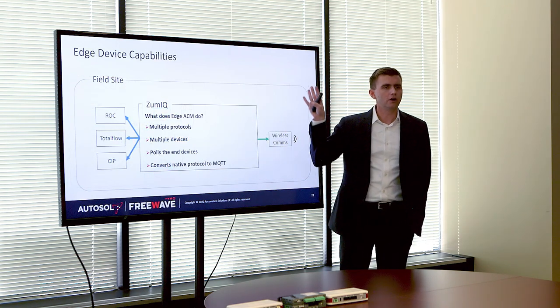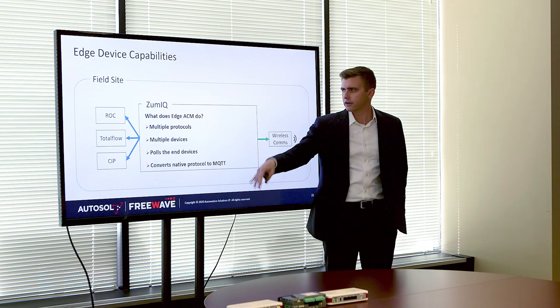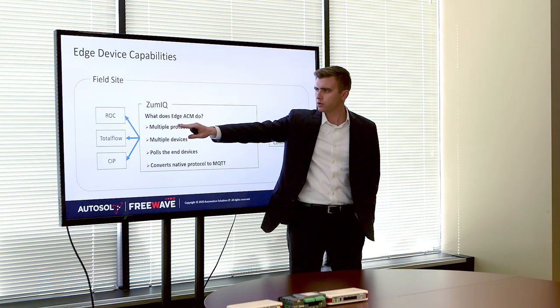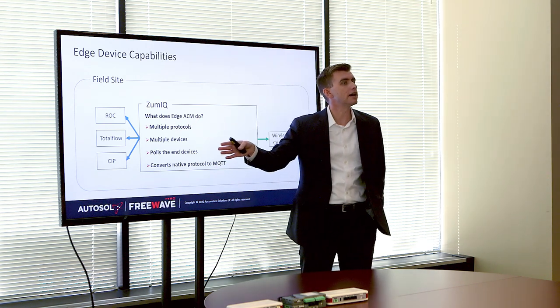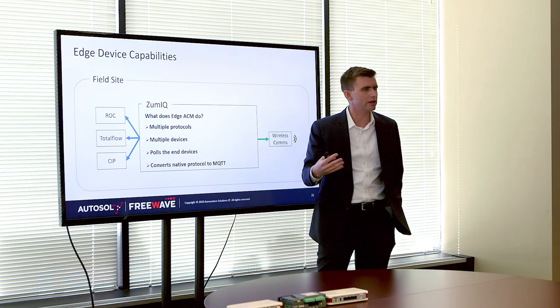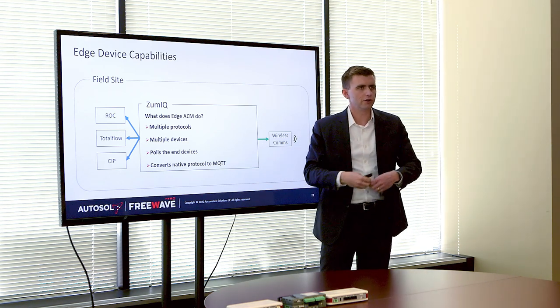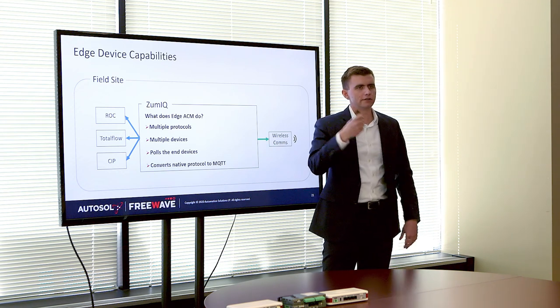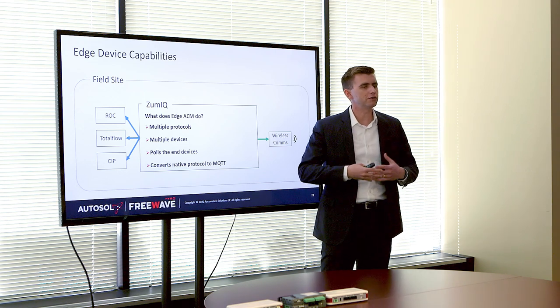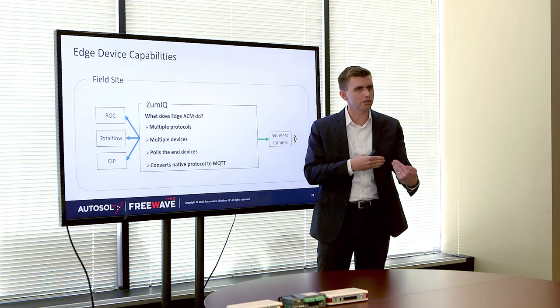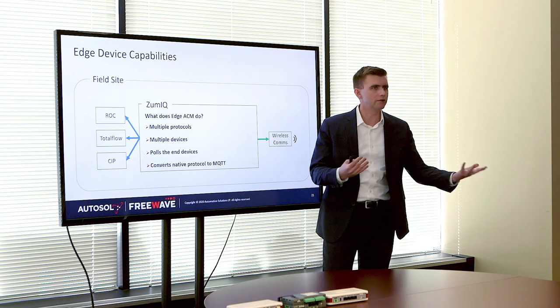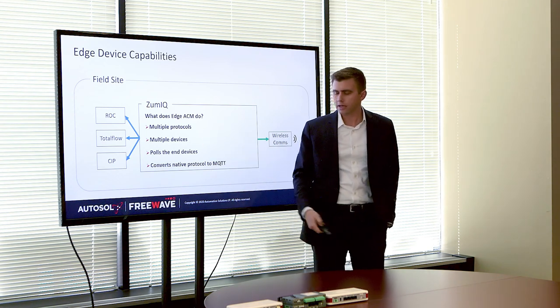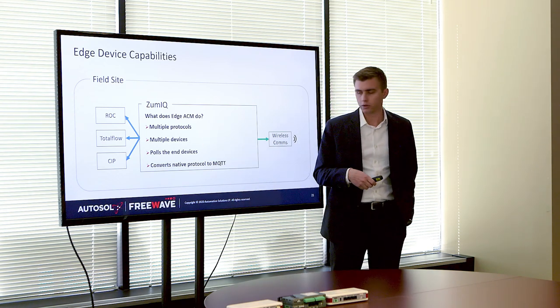To drill down more into what's happening on the edge device — here's a ZumIQ, for example. Edge ACM is pulling multiple protocols simultaneously from multiple devices. It's not where you can only pull five Totalflows or five Allen Bradleys at a time. You can do four Allen Bradleys and a ROC — you can mix and match. The only restriction on how many devices, how many tags, and what resolution is hardware-based. Edge ACM pulls multiple devices, multiple protocols, converts to MQTT or SparkplugB, and pushes that up to a broker in the field or cloud.